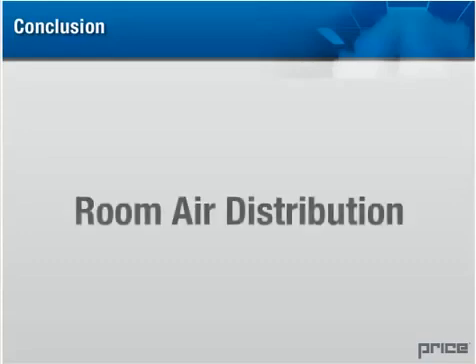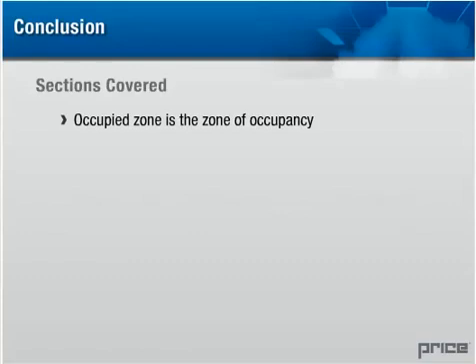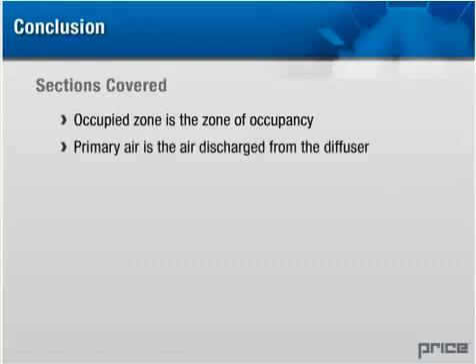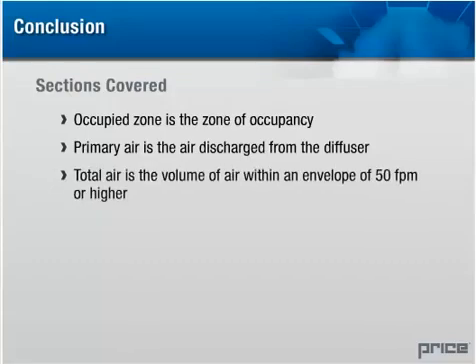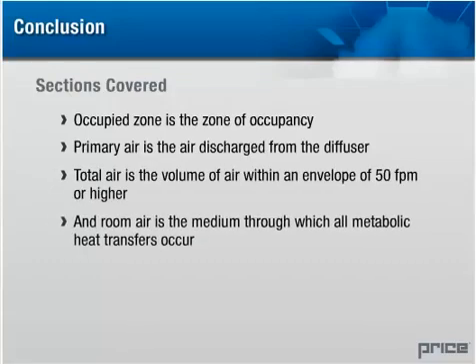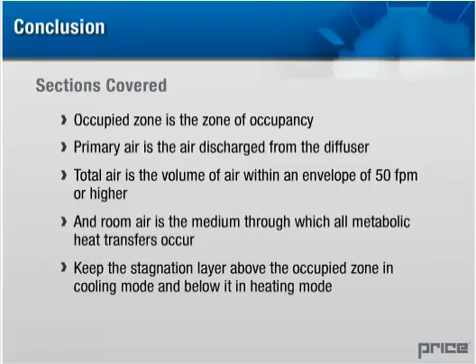You should now have a better understanding of the mechanics of room air distribution. The occupied zone is the zone of occupancy. Primary air is the air discharged from the diffuser. Total air is the volume of air within an envelope of fifty feet per minute or higher air velocity. Room air is the medium through which all metabolic heat transfers occur. Remember to keep the stagnation layer above the occupied zone in cooling mode and below it in heating mode.